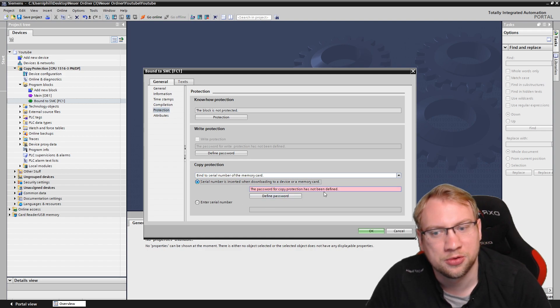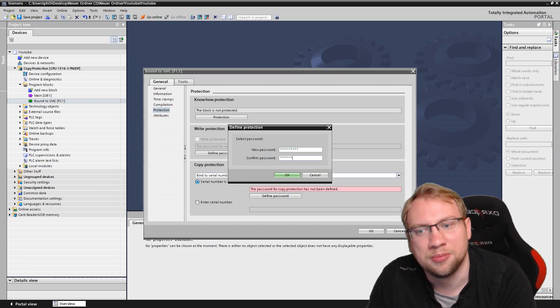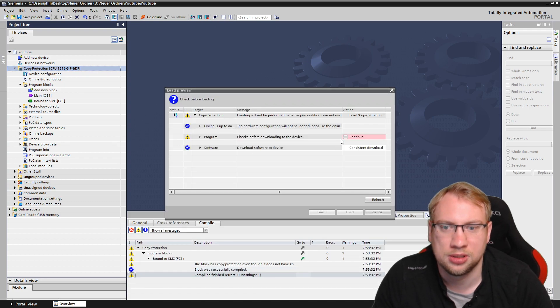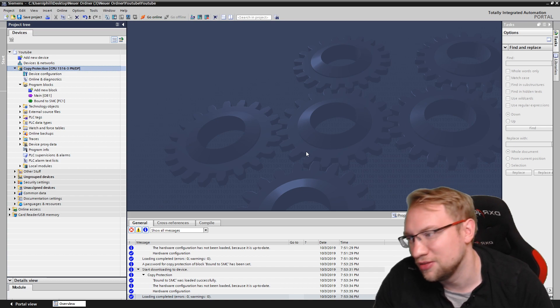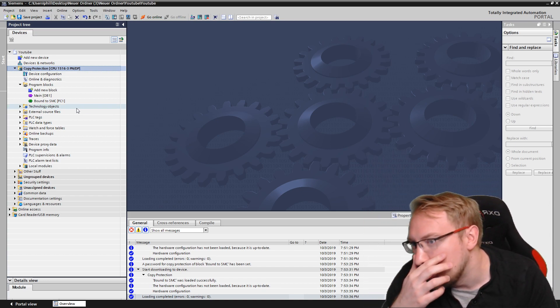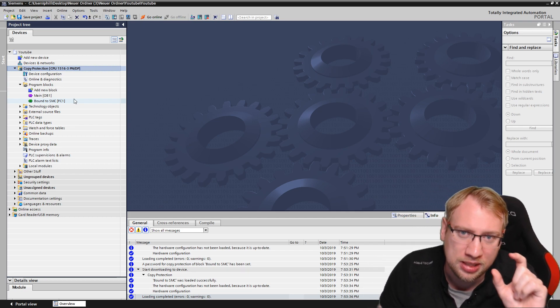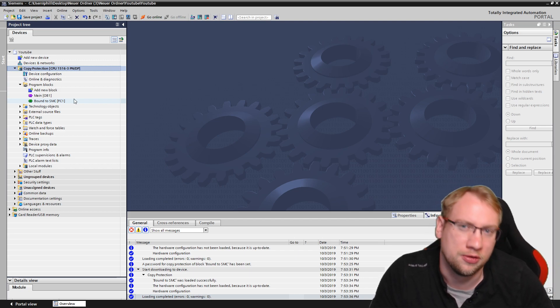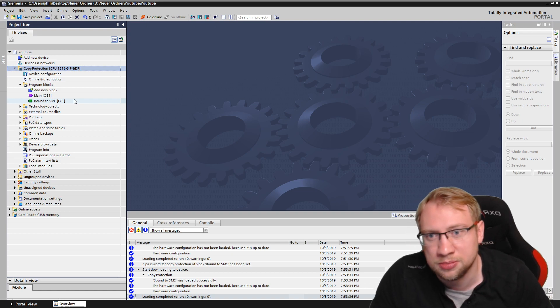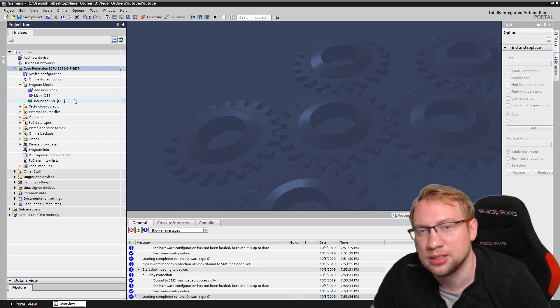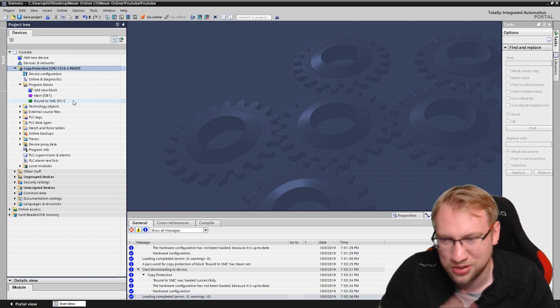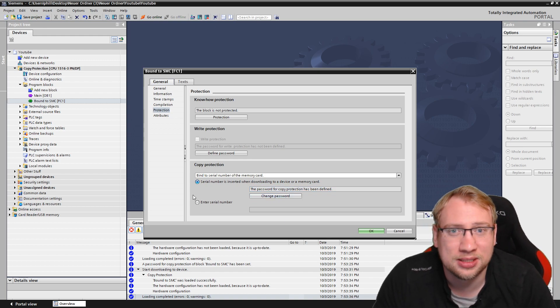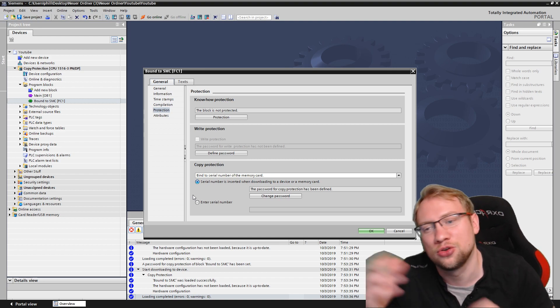The first thing I'll do is use the automatic binding option. A password for copy protection must be defined, so I set a password. When downloading, a pop-up will ask for this password. Now the program on the PLC and memory card is bound. I can take out the memory card and use it in another PLC — it will work. What won't work is taking a different memory card, inserting it, and downloading the same program to it. It's copy protected — you can still read the program from the memory card but cannot copy it to another.